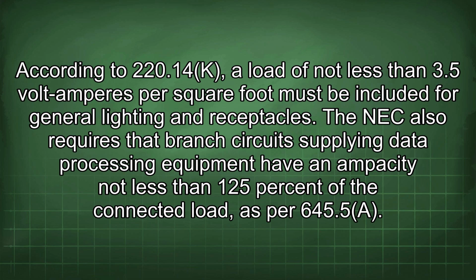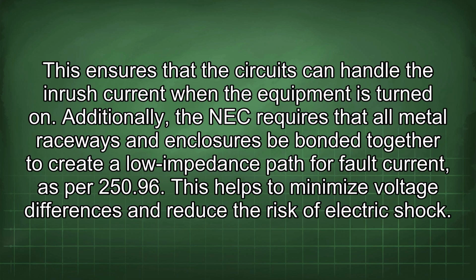The NEC also requires that branch circuits supplying data processing equipment have an ampacity not less than 125% of the connected load, as per 645.5(A). This ensures that the circuits can handle the inrush current when the equipment is turned on. Additionally, the NEC requires that all metal raceways and enclosures be bonded together to create a low impedance path for fault current, as per 250.96. This helps to minimize voltage differences and reduce the risk of electric shock.